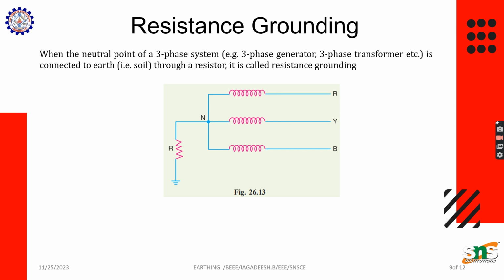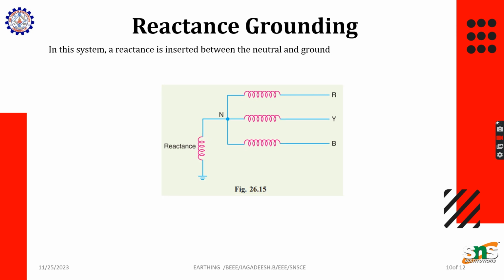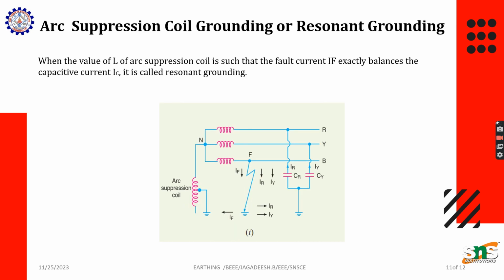The second type of neutral grounding is resistance grounding. Here we use a resistance in between the neutral and the ground. This resistance prevents the leakage of electric current which flows into the body. The third one is reactance grounding, where we connect a reactance coil in between the neutral and the ground. The last one is arc suppression coil grounding, or resonant grounding. Here we use an arc suppression coil, which is a variable one, which can control the resistance and reactance value that is to be grounded.